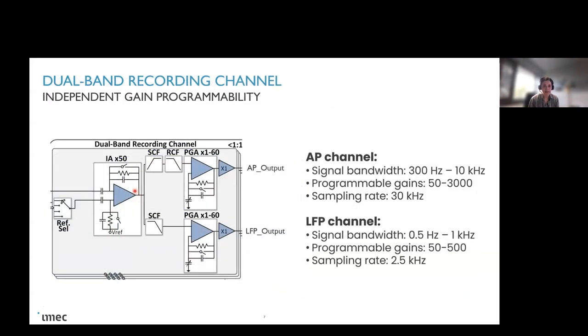As explained before, in Neuropixels 1, we are doing something that we call dual band recording. So we are separating the action potentials and the local field potentials. The idea here is that you can amplify those type of signals with different gains. This is because the action potential signals are much smaller than the local field potentials. So if you would amplify with the same gain, you will need a higher resolution in your ADC to be able to capture both signals at the same time. So for this probe specifically, we opted for having these two separate channels. It basically means that you have a double number of channels because you have only one side AP and the other side LFP, and they are all completely independent in terms of gain.